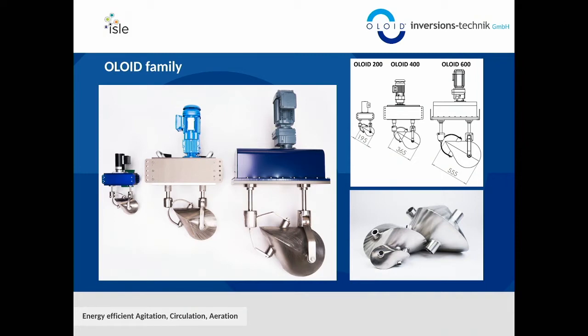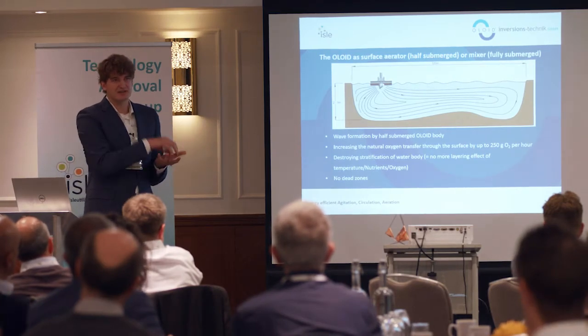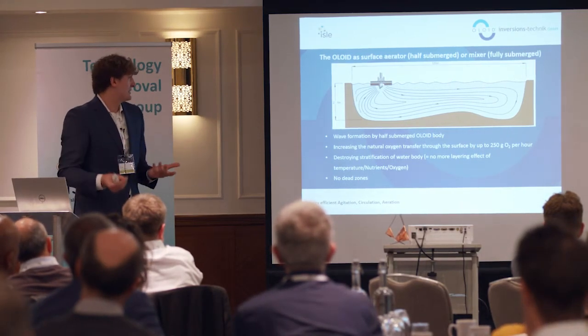In wastewater treatment plants, especially pond treatment plants, clients often use many aerators but don't have good distribution. Normally they keep adding more aeration to get oxygen everywhere, but in the end they still have dead zones. What we typically do in pond wastewater and denitrification tanks is bring the oxygen from other systems into the flow and distribute it.